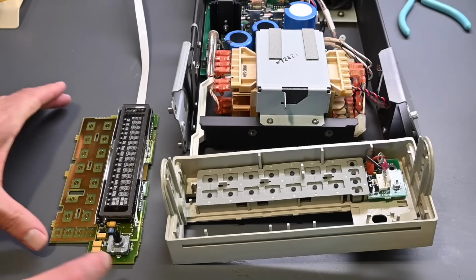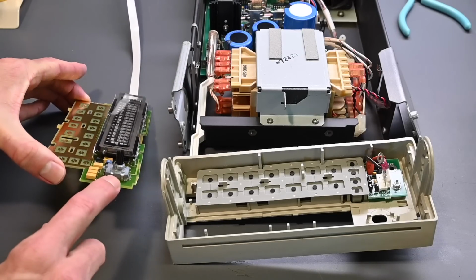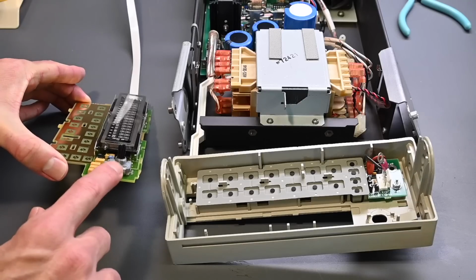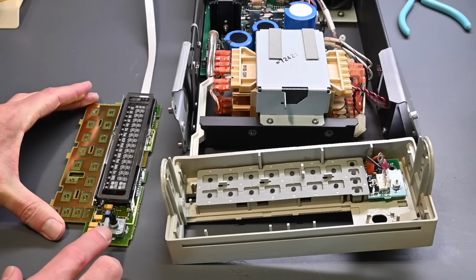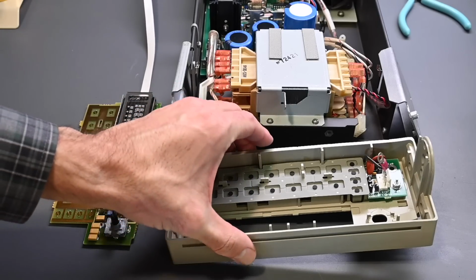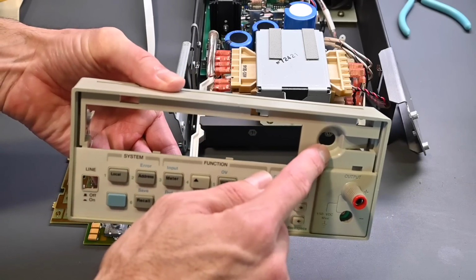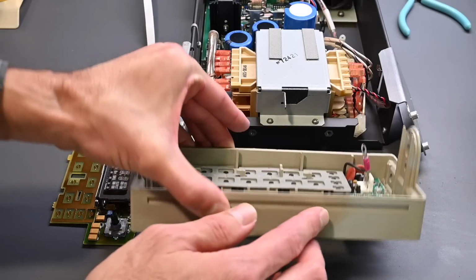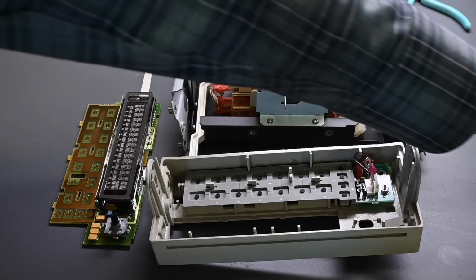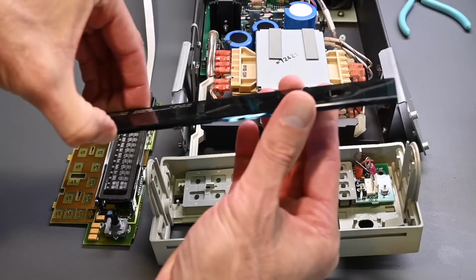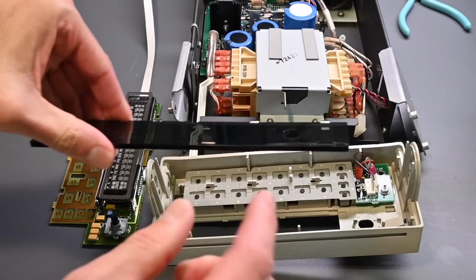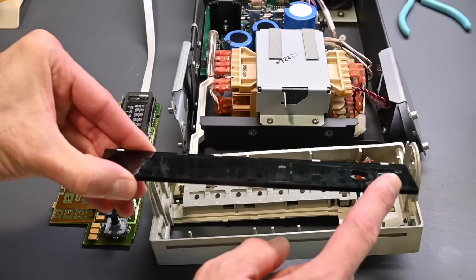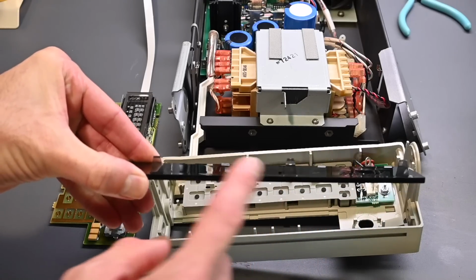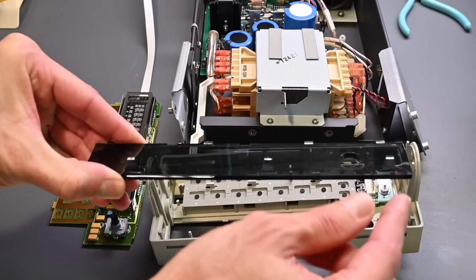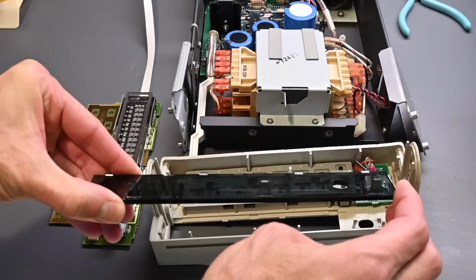And on some of these power supplies, I've noticed that there's a nut on this encoder shaft right here, but this did not have a nut on that shaft. So if there is a mounting nut on that shaft, you need to remove the display window so that you can get to that nut right here. And in this case, of course, it didn't, but on the display window, which I was removing anyways just to clean it, if you look at the back side, there are 3 clips right here, these tabs that stick out there, and this one right here. So you just press those in, and then the display window pops out from the front side.